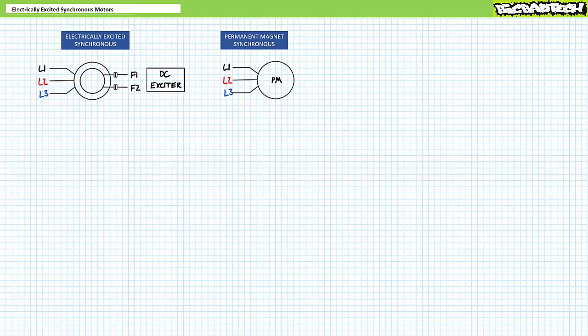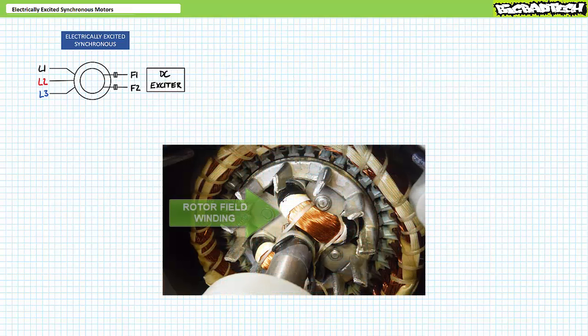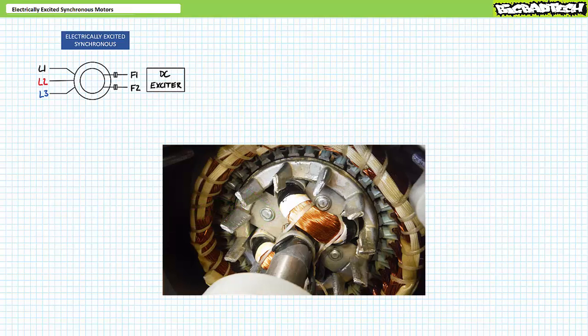Both main classes of synchronous motors feature a magnet on the rotor, the principal difference being how that magnet is established. A permanent magnet synchronous motor has a permanent magnet on the rotor and necessitates no additional accessory electrical connections. Whereas an electrically excited synchronous motor features a coil of wire on the rotor core called the field winding, connected between terminals F1 and F2. When the field is energized by an external DC source known as an exciter, it establishes an electromagnet where the strength of the resulting magnetic field is proportional to the current flowing through the coil. More DC current means more magnet; less DC current means less magnet. Once established, the rotor electromagnet locks in with the rotating stator magnetic field and follows it around, matching the synchronous speed. For the purposes of this lecture, we're presuming the DC exciter is an external DC voltage source, like an independent battery.